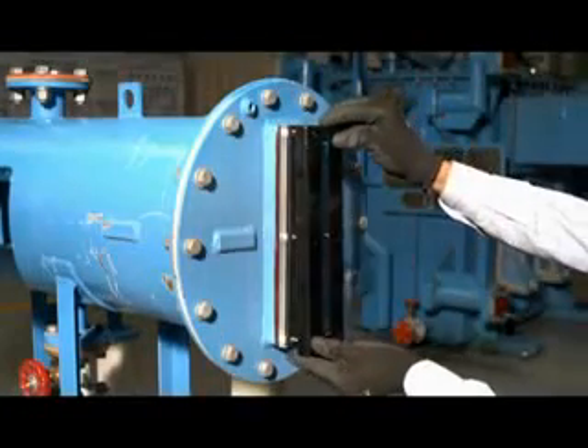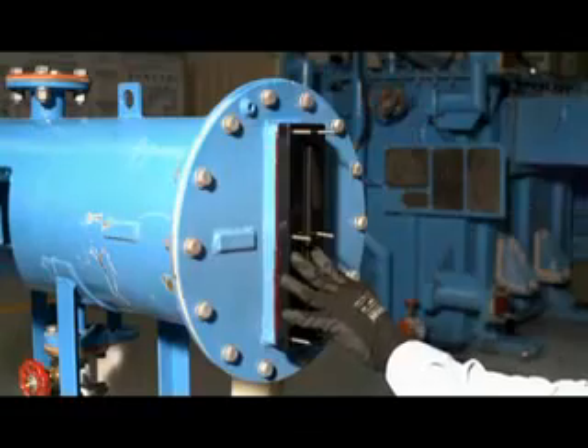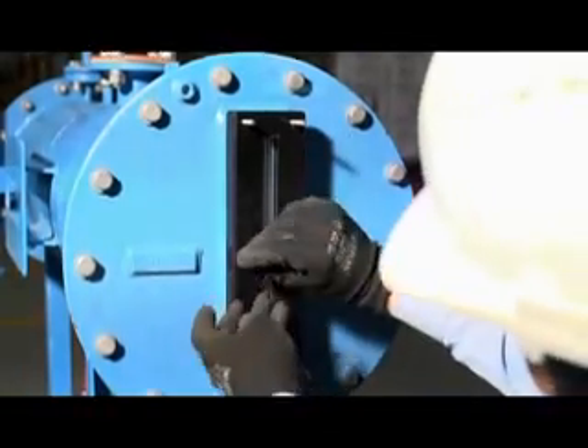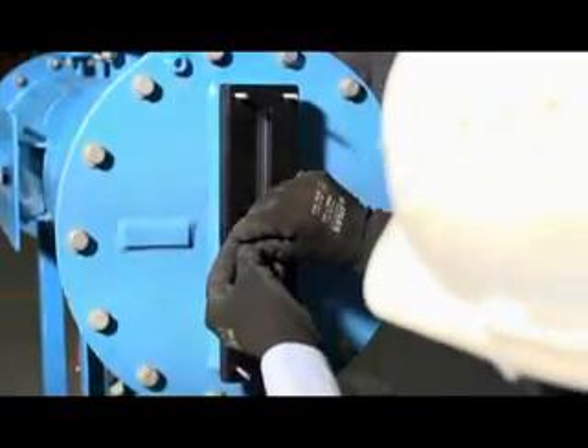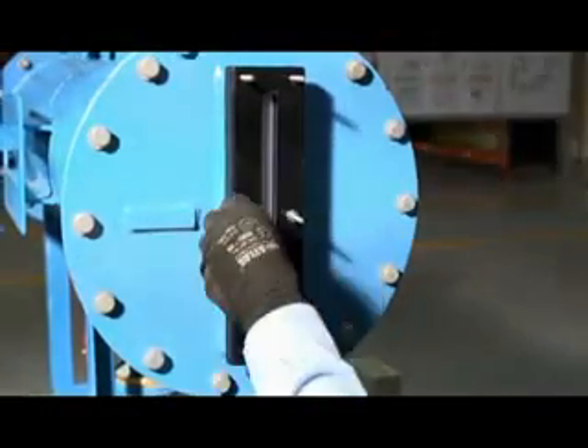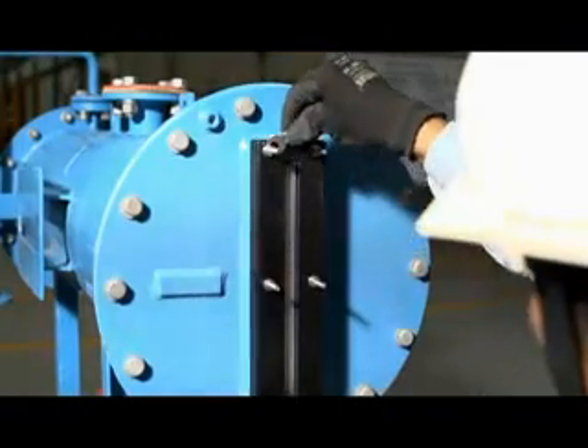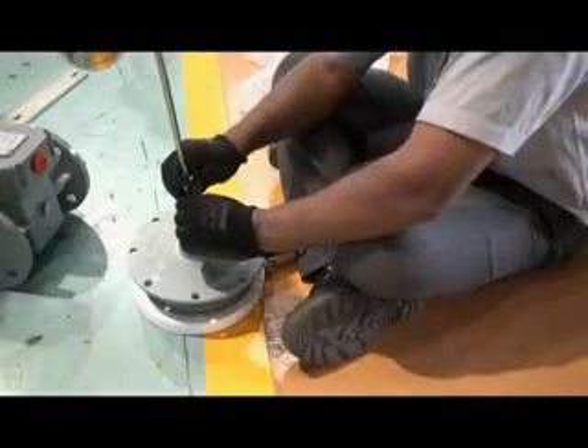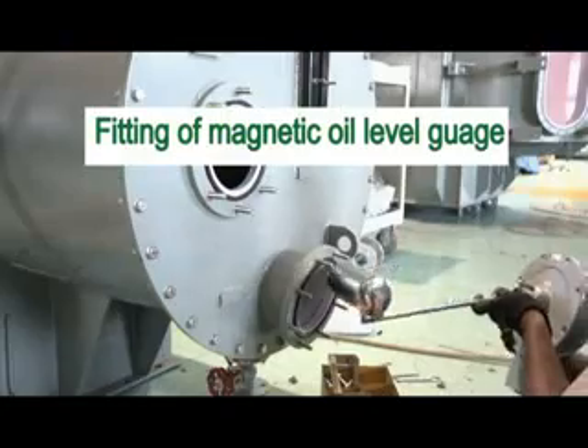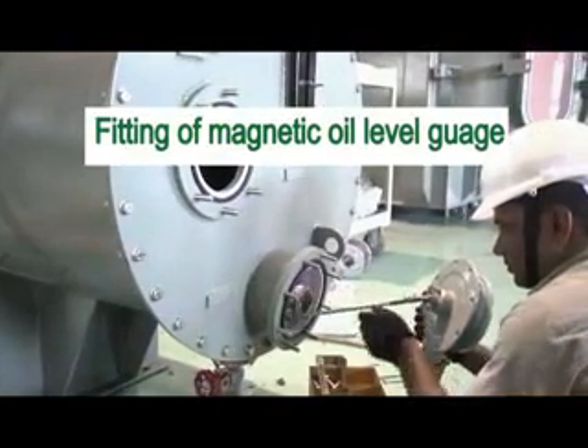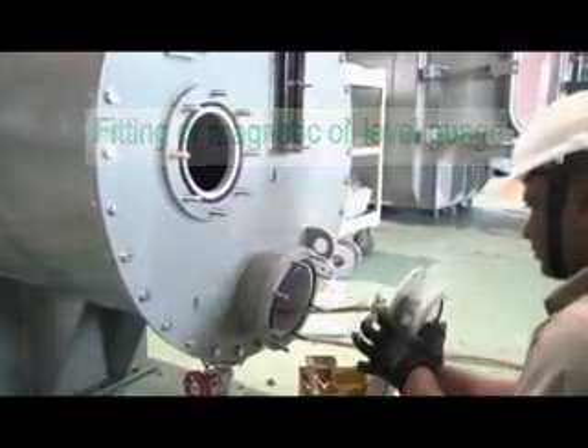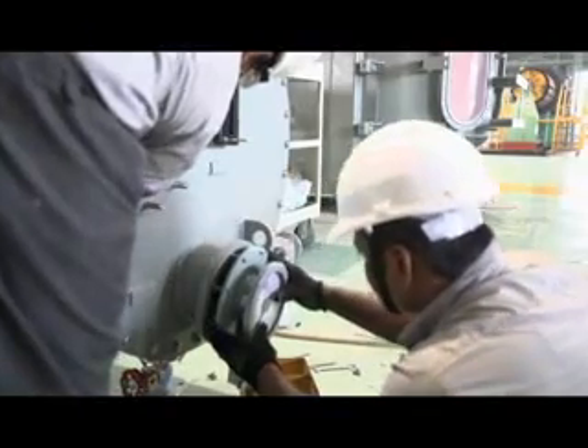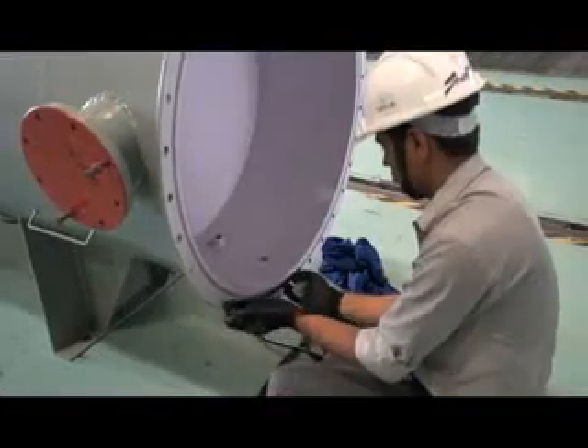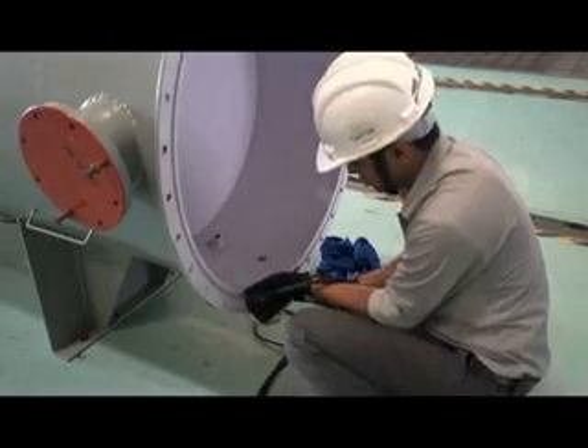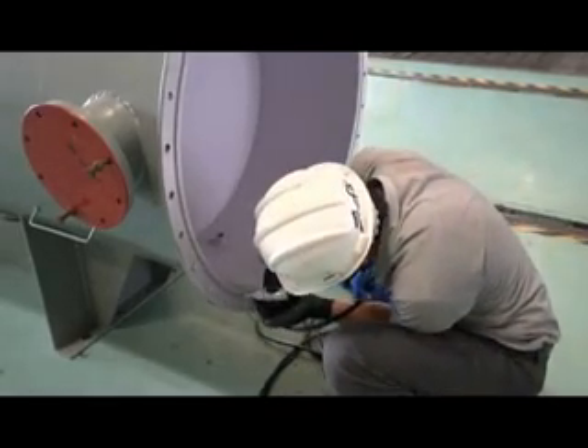It is normal practice to use magnetic oil level gauge with low level alarm and trip contacts. This can also be of the plain glass or prismatic type. The oil level gauge is marked to indicate minimum, normal and maximum oil levels in the conservator as a function of conservator capacity. The conservator or partition for an on-load tap changer carries its own oil level gauge. For bigger units, it is our standard practice to fit a normal oil level gauge on the tank also.